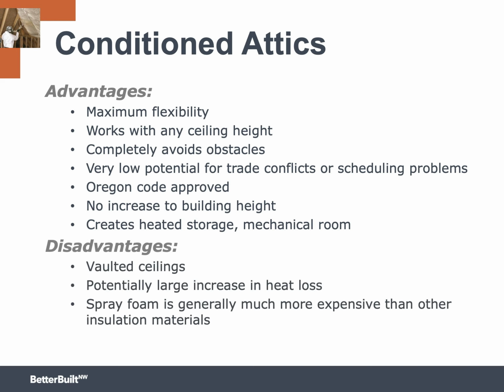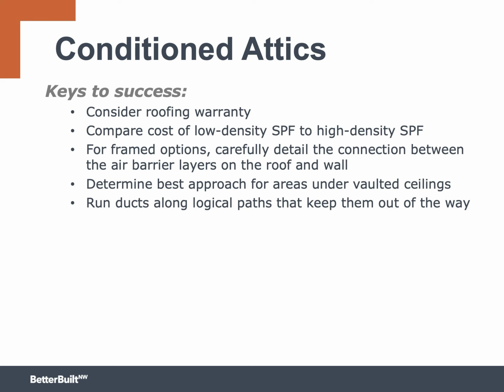If you want to enjoy vaulted ceilings or high ceilings, you won't be able to use that space for ducts. There's a potential increase in heat loss. Again, it's probably not as much as you're saving from moving the ducts inside, but you are increasing the volume of the building. If you choose spray foam, consider this. It may be more expensive than other approaches. Plus, conventional spray foam has a very high global warming potential. There are relatively new options with low GWP, so check out HFO spray foams.